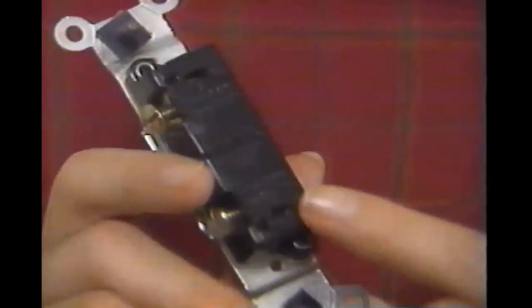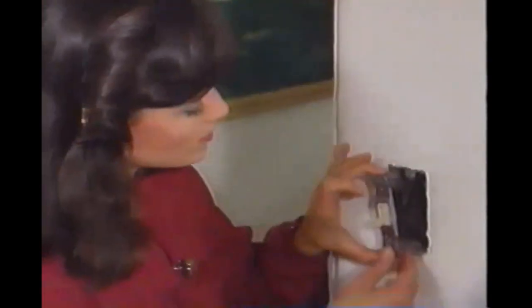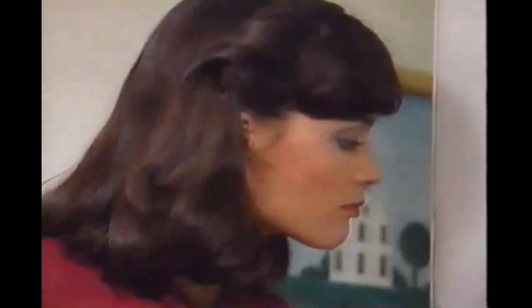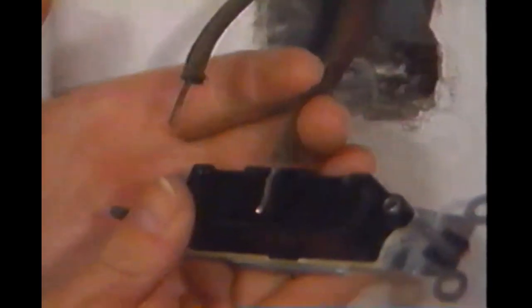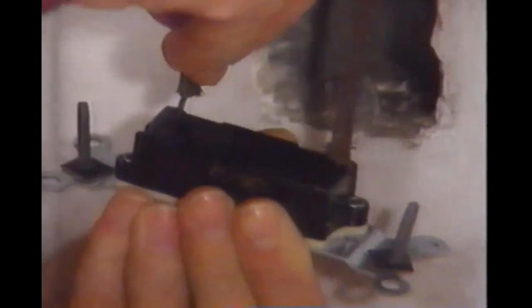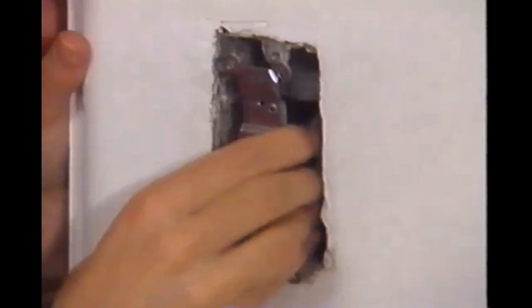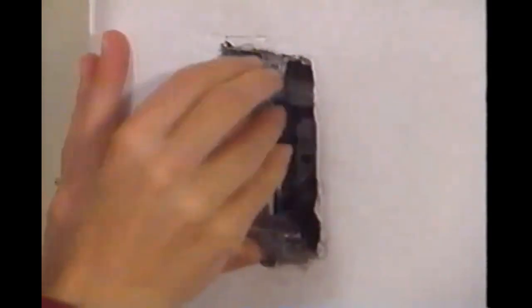Back-wired switches are the easiest and fastest to install. Unscrew the switch and pull it out of the box. Push a small bladed screwdriver into the wire release slots, then pull the wires out. Cut the house wires blunt, strip them using the guide on the back of the switch, and insert them into the slots. Then fold wires in, place switch into box, fasten and install cover.